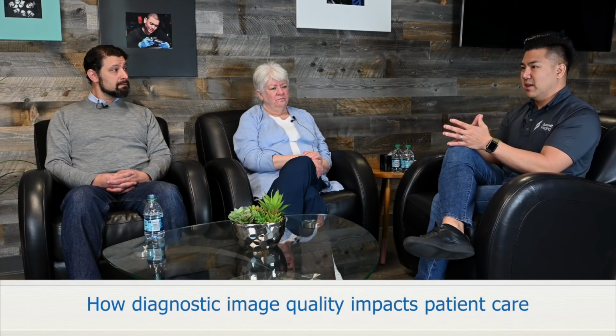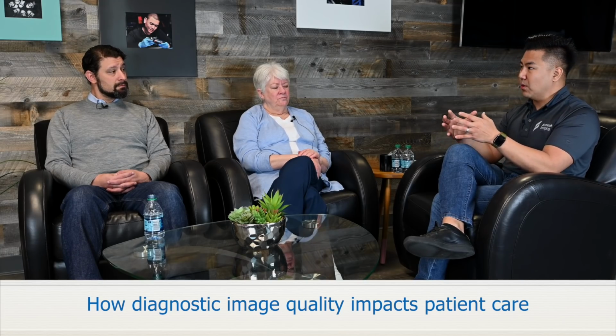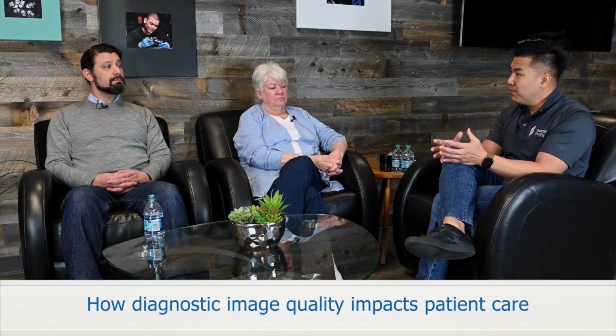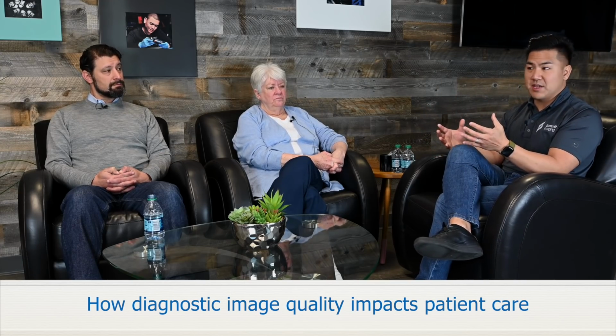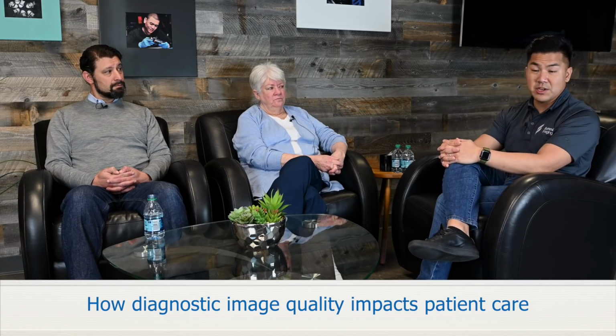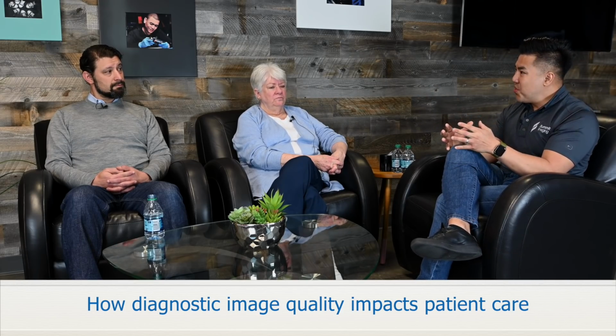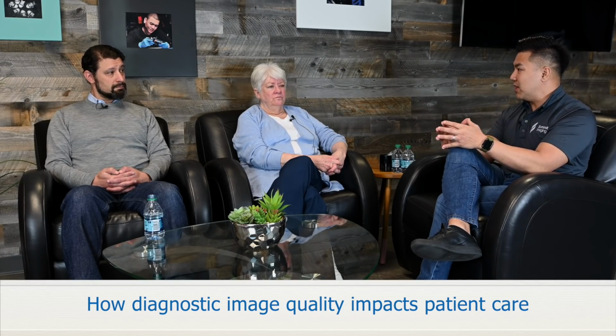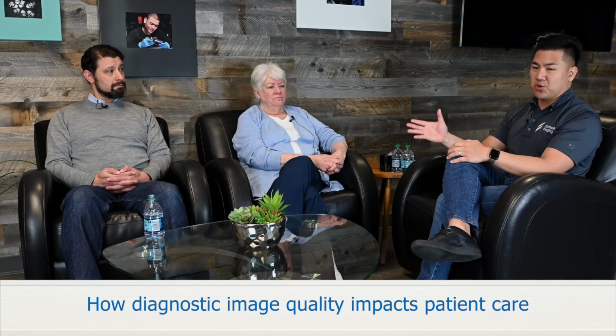Let's chat about the patient and what your thoughts are, because of the degraded resolution. I think what's really interesting here, just to kind of throw into the conversation, is that the regulation right now for transducers is acoustic power, and there's actually a lot of information about that on the FDA website. Link down below if you are interested. But there's no regulation around the quality of the image, and so the acoustic power determines penetration. So we really weren't surprised that the penetration capability of these counterfeit crystals that we're talking about was very similar to that of the correct OEM crystals.